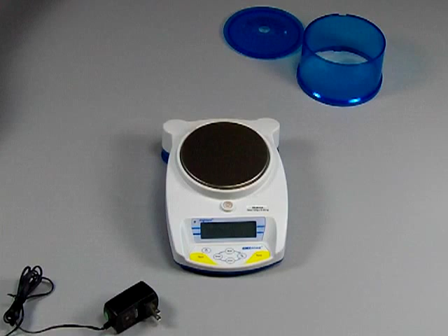Another unique feature for this price category is the scale has internal calibration. So if I turn the rear of the scale to the camera, you'll see that there's a little lever here, and one just moves it over to drop the calibration weight to do the calibration. So this scale does not have motorized internal calibration. It has a manual lever that drops the calibration weight, and that's a real unique feature for this price category.